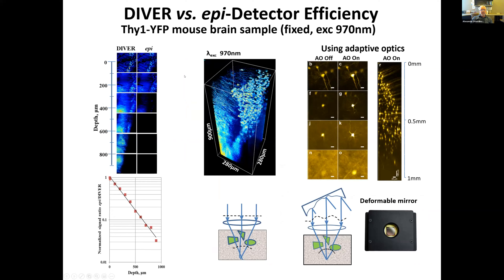We did the same experiment with actual brain tissue, imaging it with both DIVER and epi detectors. With the epi detector, images practically disappear after about 400–500 microns depth. With the DIVER detector, we still get pretty bright images. Also, at shallow depths the images are very sharp, but going deeper they become blurred — exactly due to wavefront distortion of the excitation beam that I described earlier. We used adaptive optics in our system, which improves the image quality at depth to some extent.